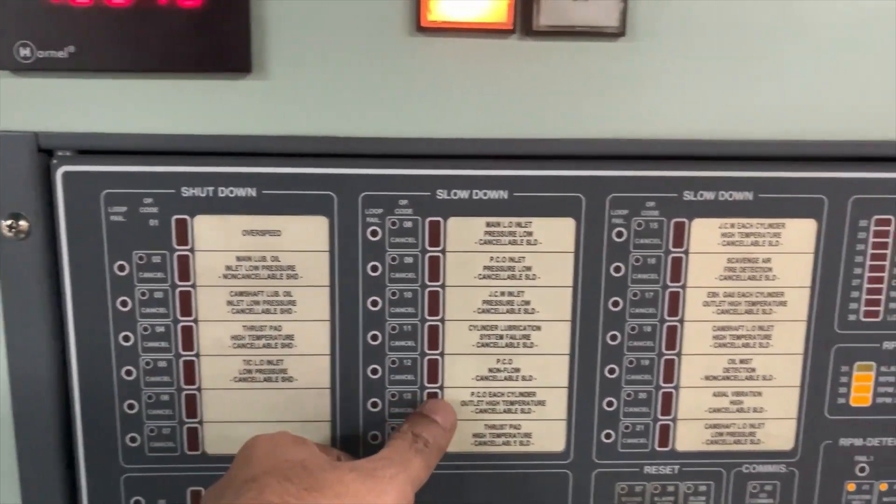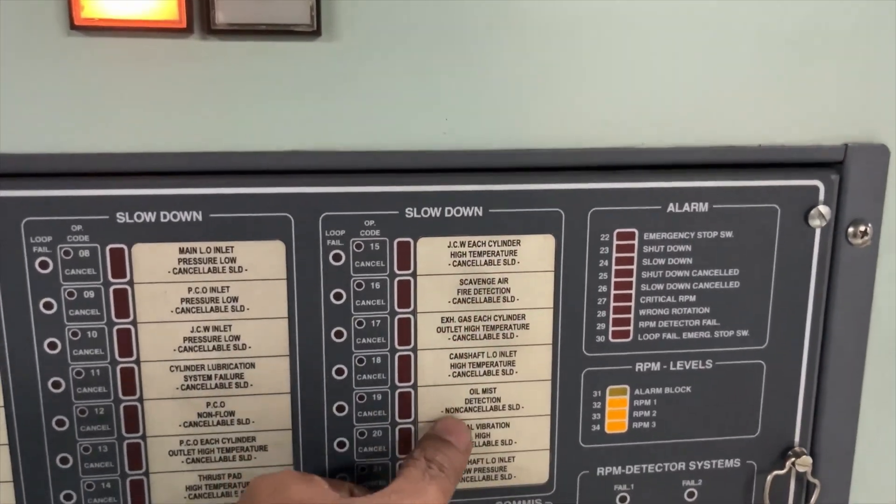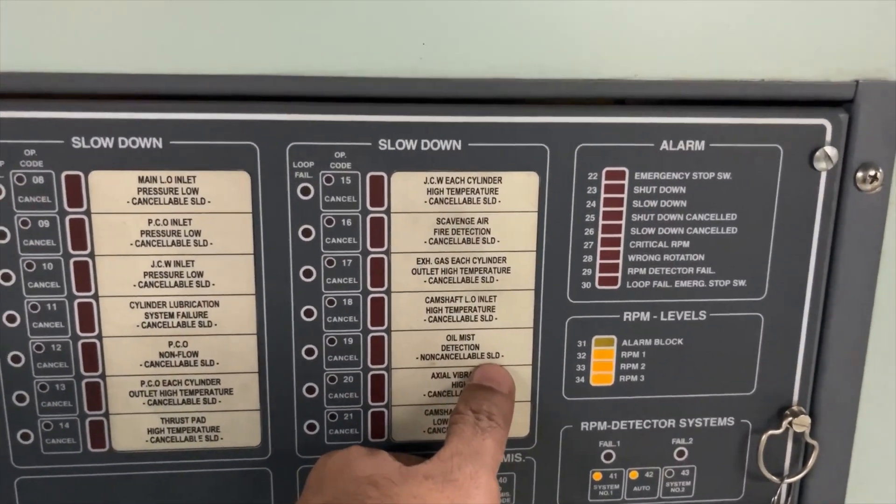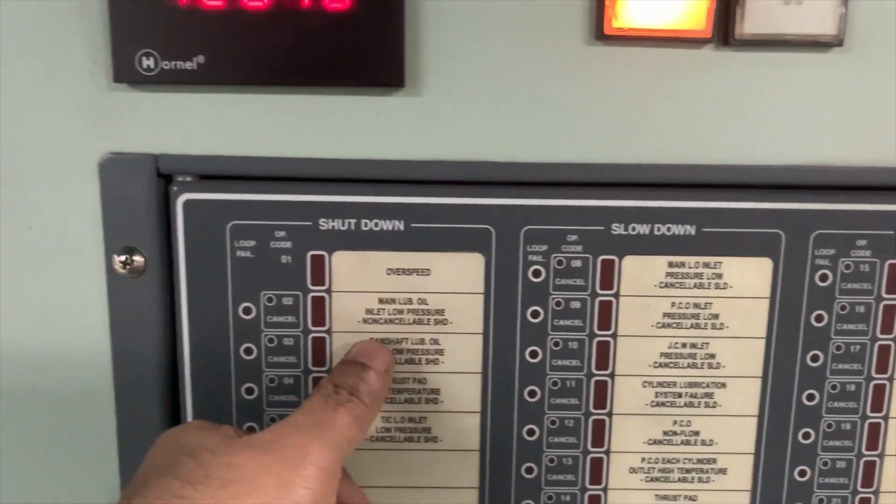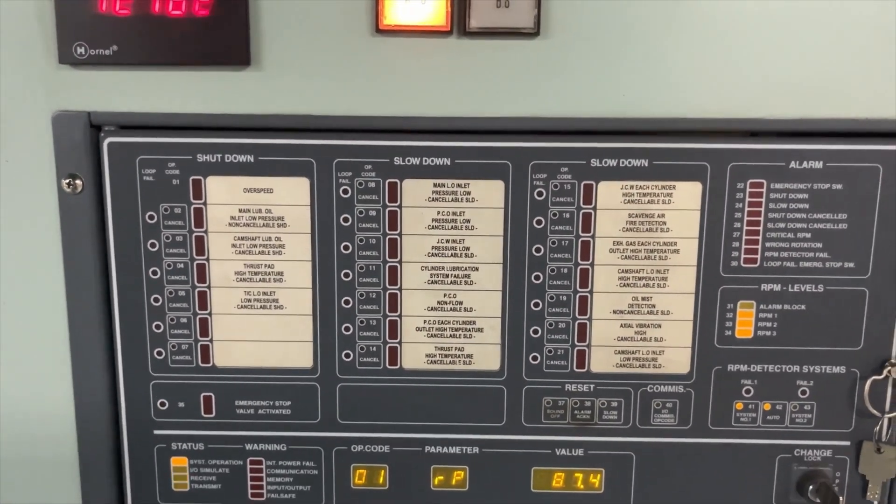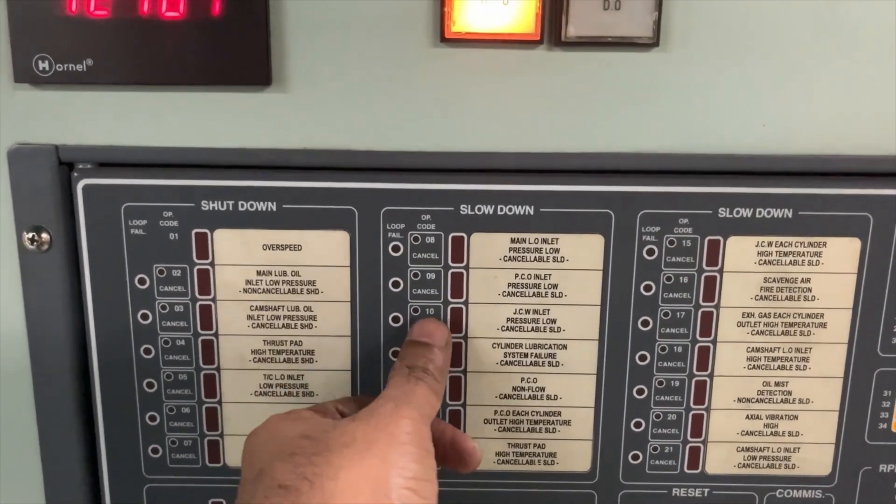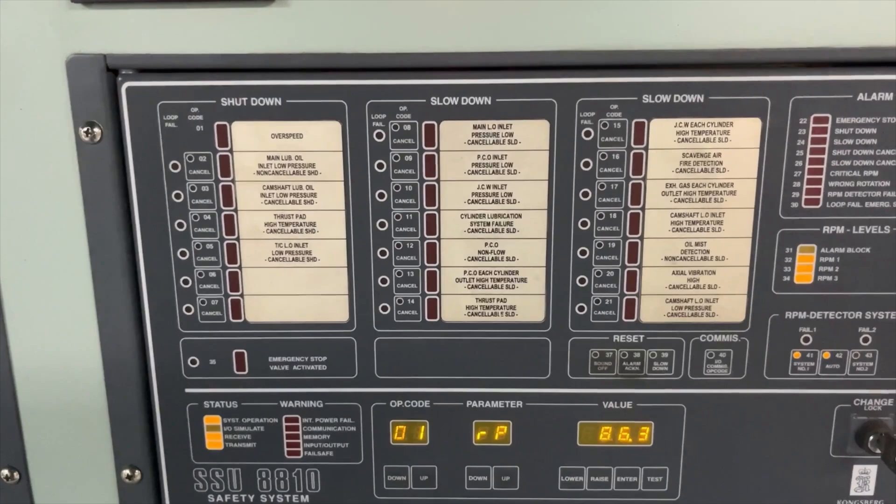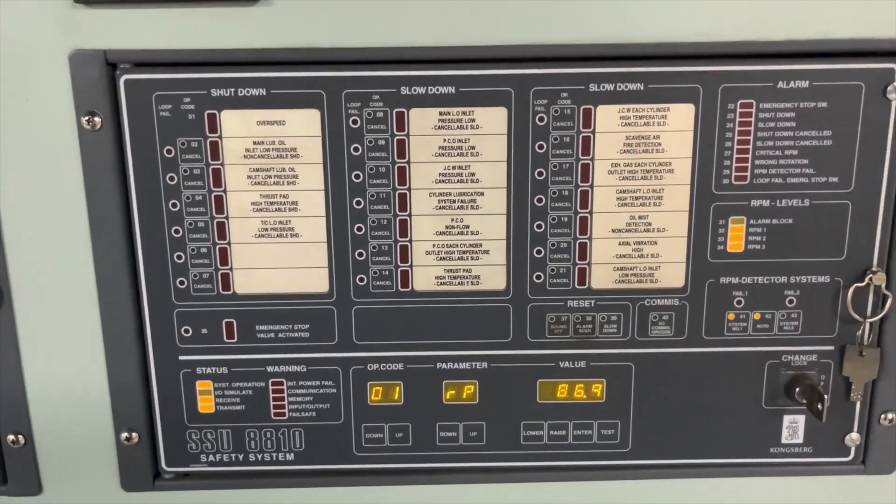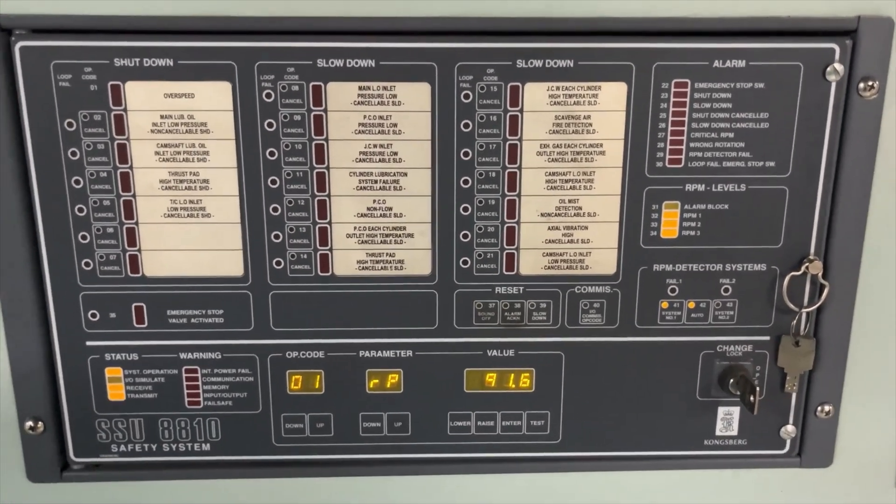These alarms you can cancel. But these few alarms, this is oil mist non-cancellable. And main engine lube oil inlet pressure, this is non-cancellable. Other alarms, you can press this cancel button and cancel them and you can run the main engine. But once these alarms are activated, you will not be able to run it.